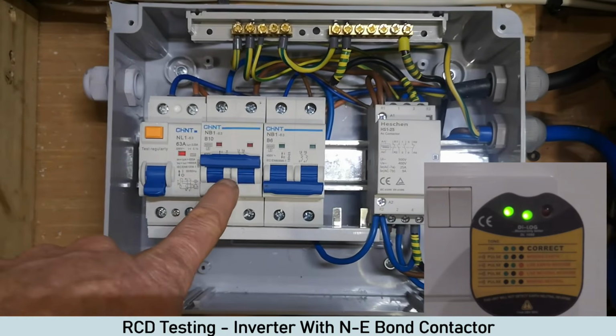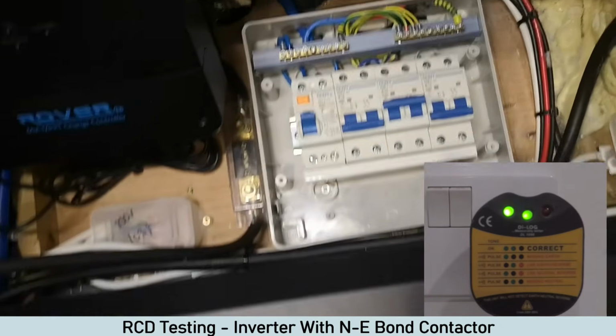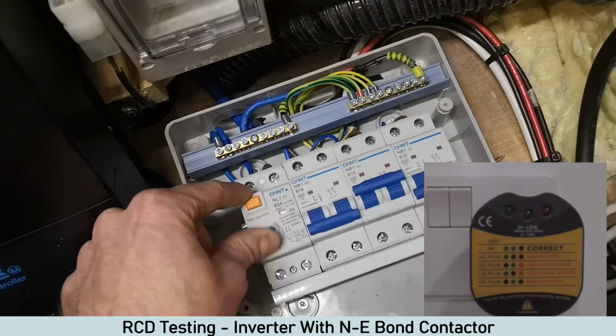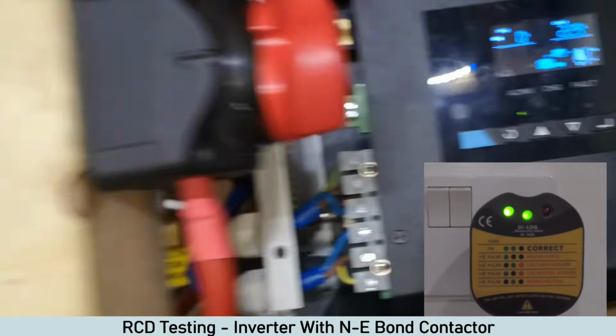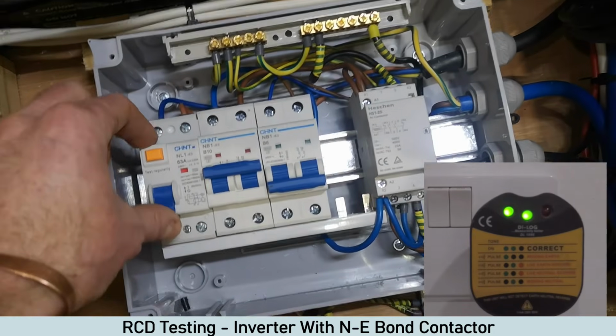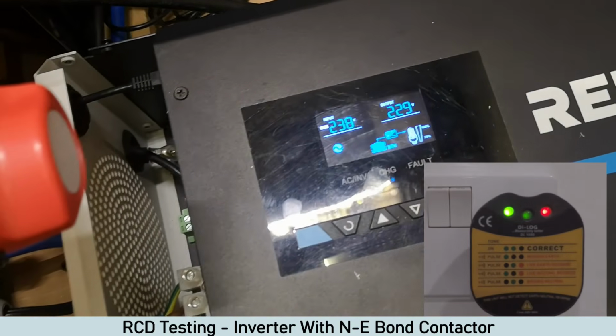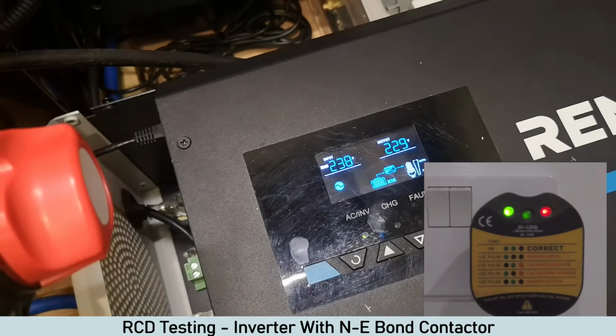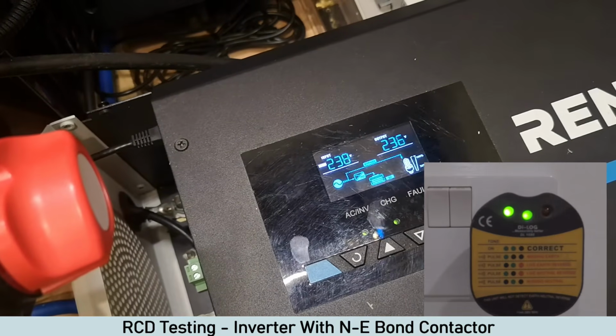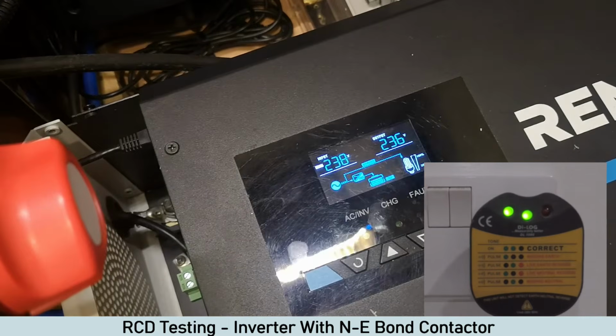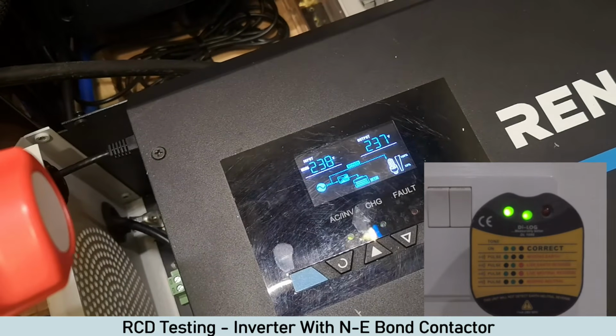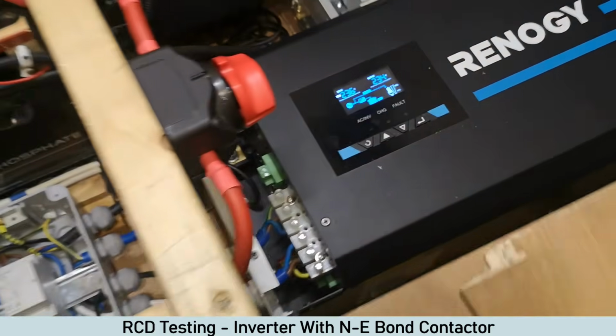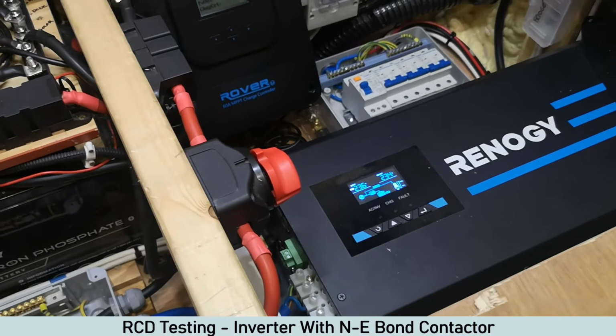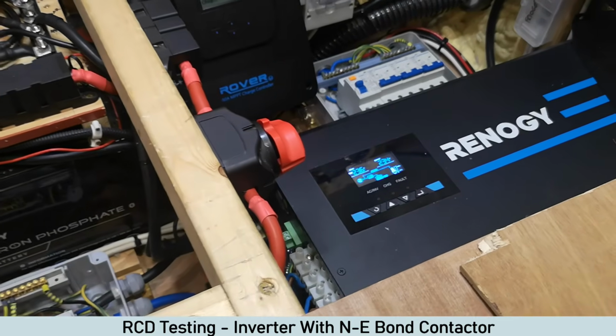So the power's off here, and obviously we've still got power there. Trip that out. So what I'm going to do now is turn this on. That will come on straight away. That will take a little bit of time. So let's switch that on. Contactor's on. So now you can see that the socket tester is actually in fault because it's in center tap mode. And there we go. Once it's in bypass, the RCD works. So it's functioning well. The only issue is that few seconds of time where it's obviously in center tap mode.